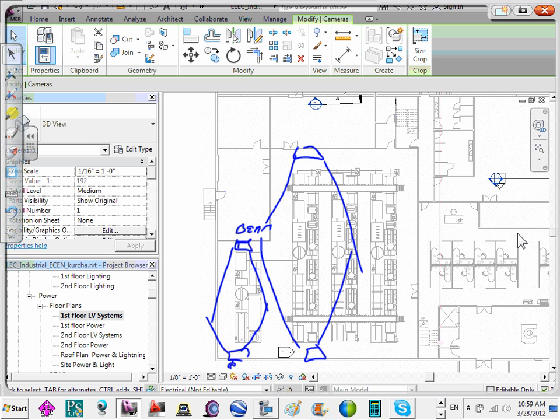Other options that you can do is, we talked about before, the VESDA, a 4-pipe system, which is just an air sampling system, and you can have a maximum of 60 holes per pipe, and you can go 2,500 feet. And the way I would, if I was going to put a VESDA system in here, it's a pipe system, starts here, goes up to the ceiling, and we always have it come down, put the end cap down here, probably about 6-7 feet. Why? Because the end cap is where they're going to do the testing, so you can just go there right at the end and spray the pipe instead of going all the way up to the top.